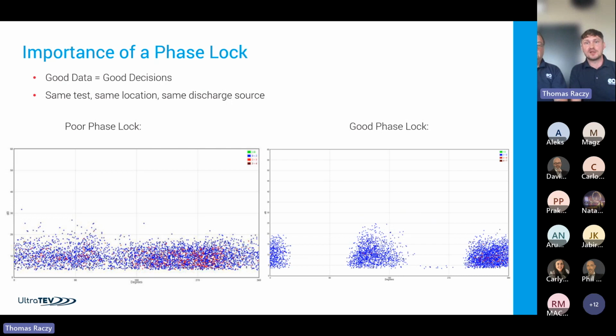So the lock to the mains frequency, as Andrew mentioned before, is primarily achieved by default by the photosensor included in the UltraTEV Plus. On the left-hand side, we've got the absence of phase lock. This was done on purpose. There's a discharge there. Both screenshots show discharge from the same source, the same location, and the same sensor was used.